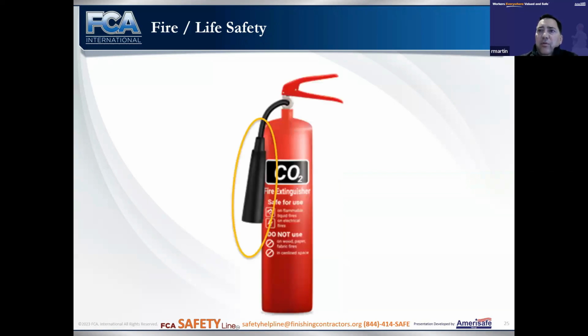CO2, the key to the CO2 fire extinguisher is this bell-shaped nozzle. If you see one of those, you don't have the right fire extinguisher on this job. Note that it says do not use on wood, paper, ordinary combustibles. Also, don't use it in confined spaces. This fire extinguisher extinguishes fire by pushing oxygen away and out from the burning area. If you're in there, that's less oxygen for you to breathe. And because ordinary combustibles tend to smolder, the moment oxygen rushes back into that burning area, the fire reignites.